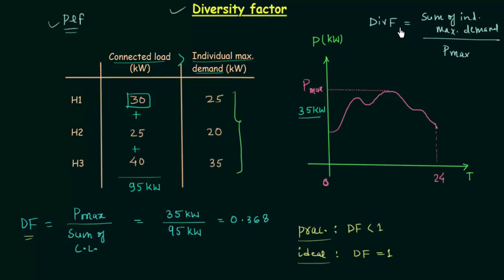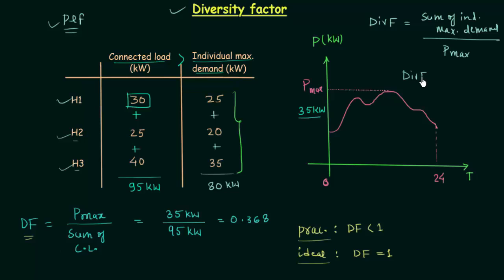Using this we will calculate the diversity factor for this particular case. The individual maximum demands occur at different times — house number one will not have its individual maximum demand at the same time as house two and house three, and the same applies to the second and third houses. The sum of individual maximum demands is 25 plus 20 plus 35, which equals 80 kilowatts. So the diversity factor is simply 80 kilowatts over 35 kilowatts, which gives 2.28, and it is greater than 1.